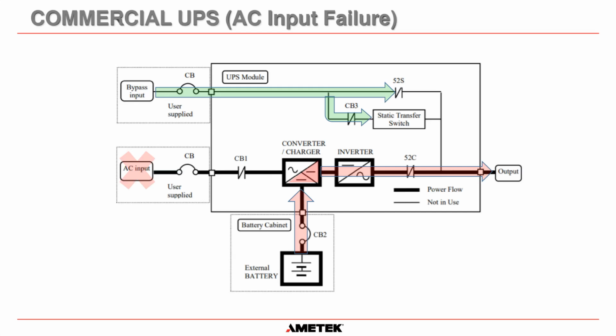So in a commercial UPS, if you have an AC input failure, if the power fails, then the charger switches off. But it's just like you unplugging the plug from your laptop battery. Your laptop still carries on without any issues whatsoever. It doesn't switch to battery. What it does is the battery just takes over as the DC from the charger collapses, and maintains the DC into the inverter. So the power flow is now from the battery through the inverter and out to the output.